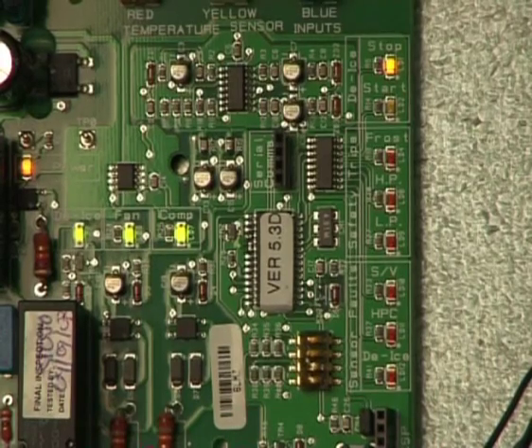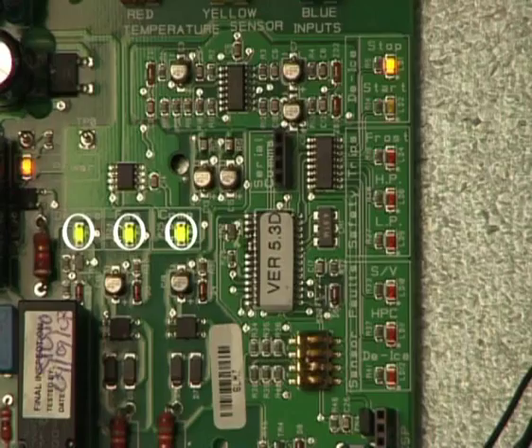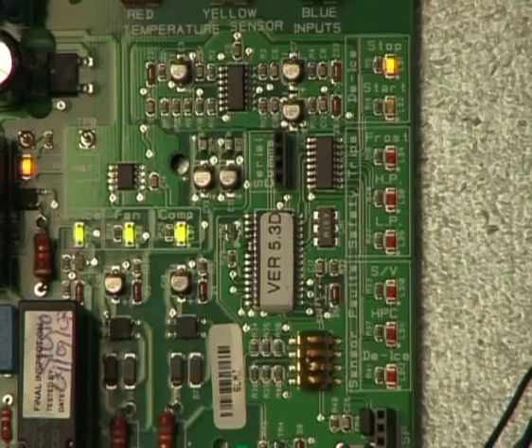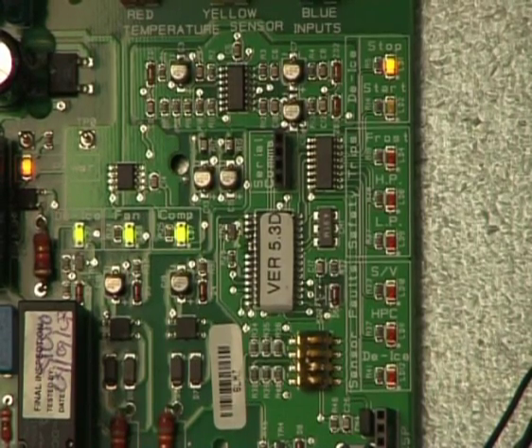Let's run through the various LEDs and their functions in detail. Firstly, we have 3 operation status green LEDs, which are located towards the centre of the OUC. These particular LEDs indicate current running status of the de-ice cycle, condenser fan and compressor. It is always best to check these LEDs when troubleshooting, as they are clear verification as to what should or should not be running. There are also a series of LEDs located on the far right-hand side of the OUC. These LEDs indicate de-ice status for reverse cycle operation, as well as various safety trips and sensor faults.